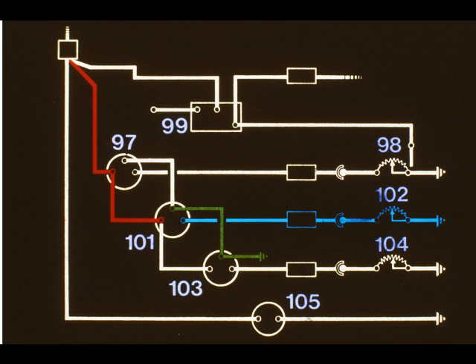Let us assume that we're going to test the temperature gauge. Before connecting the test unit, first check the continuity of the lead connecting the instrument to the battery, shown in red, the lead connecting the instrument to its sender unit, blue, and the earth connection, green. Now test the instrument in situ by substituting the test unit for the sender.